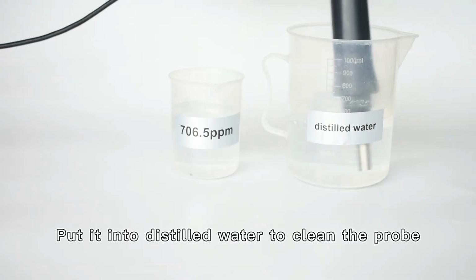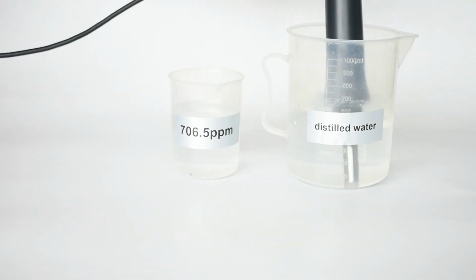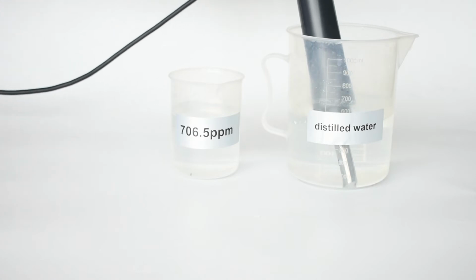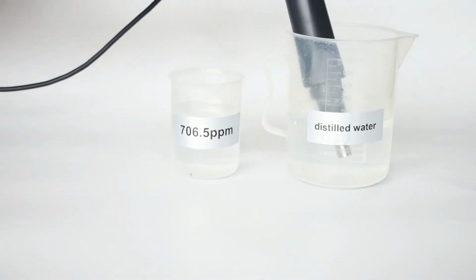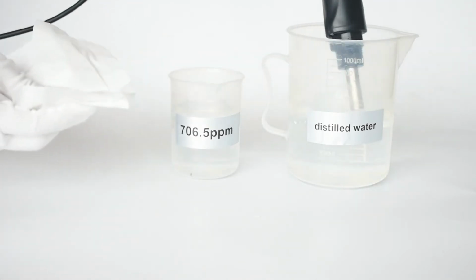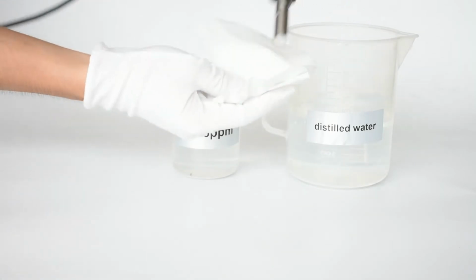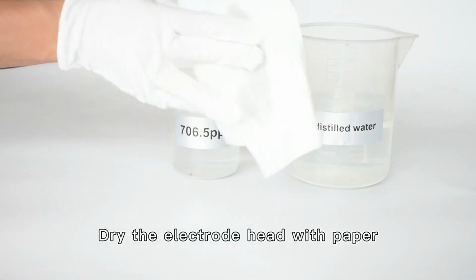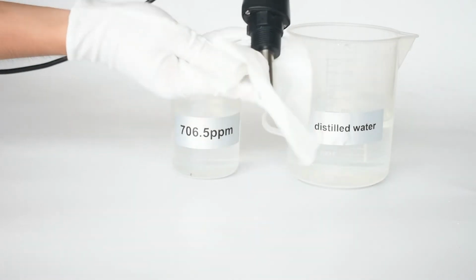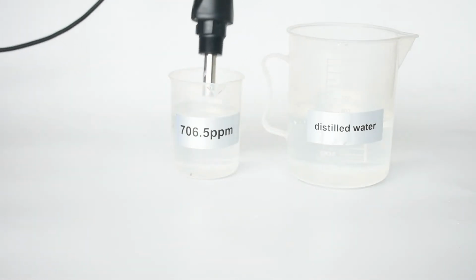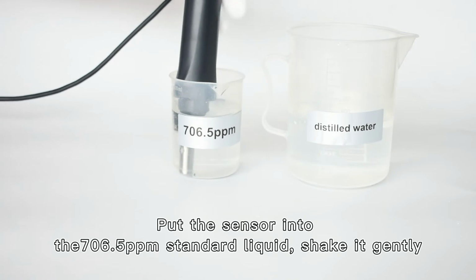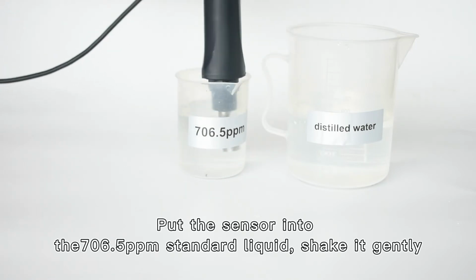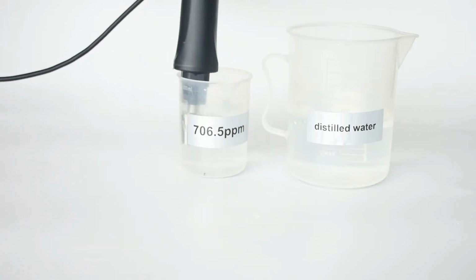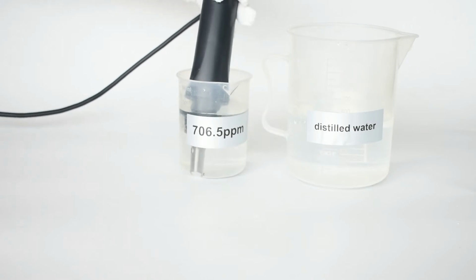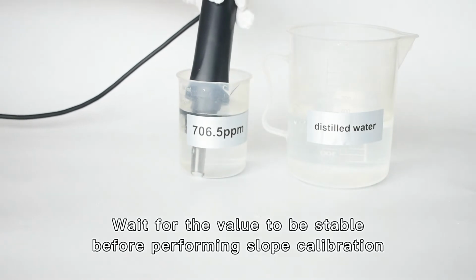Put it into distilled water to clean the probe. Dry the electrode head with paper. Put the sensor into the 706.5 ppm standard liquid, shake it gently. Wait for the value to be stable before performing slope calibration.